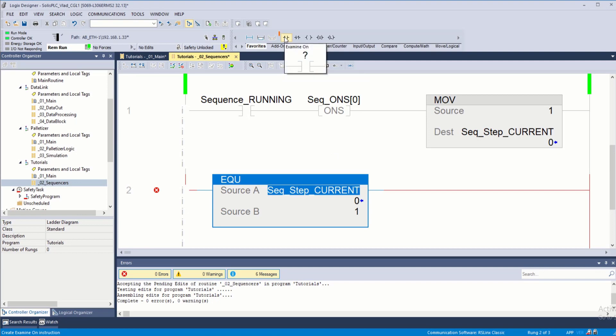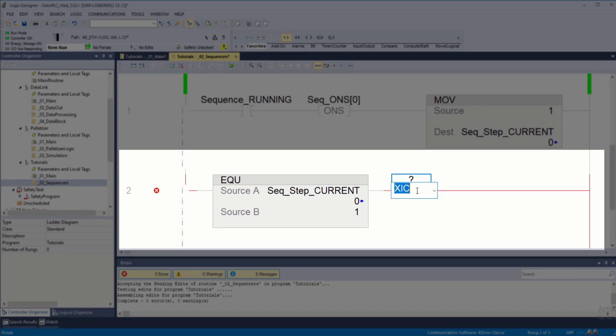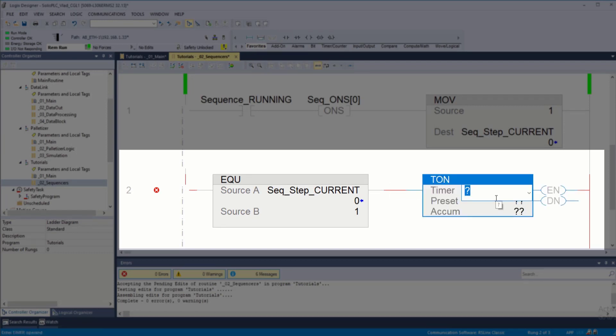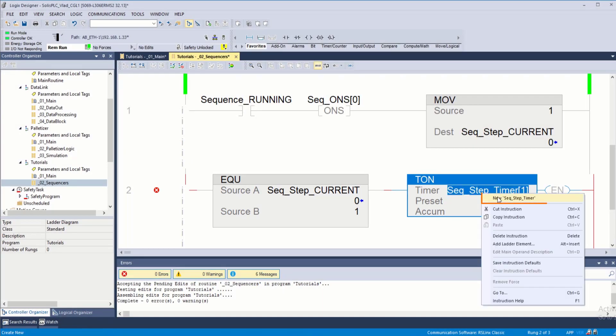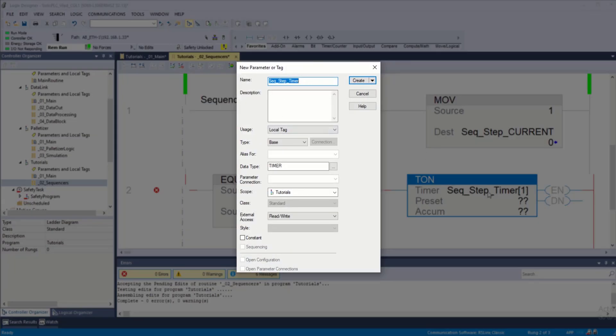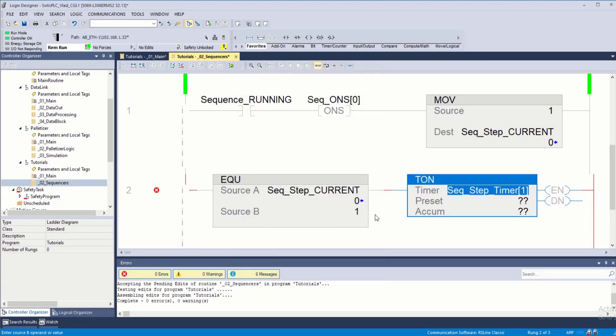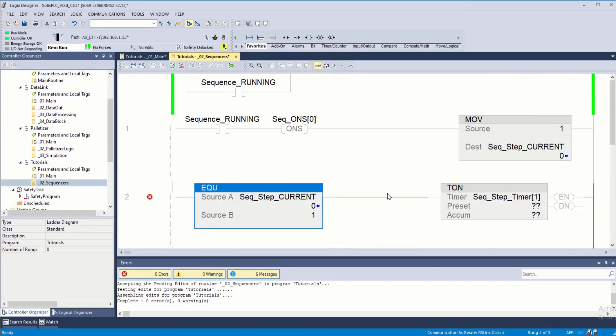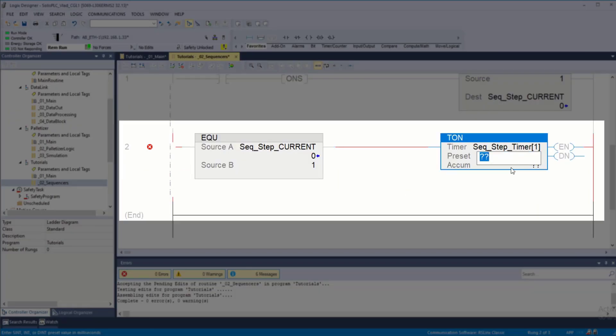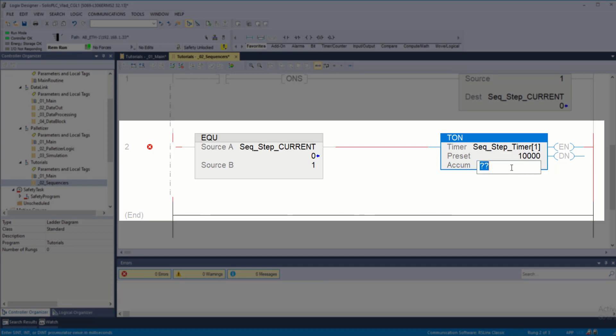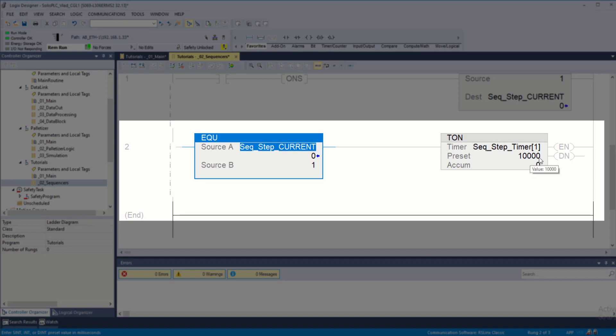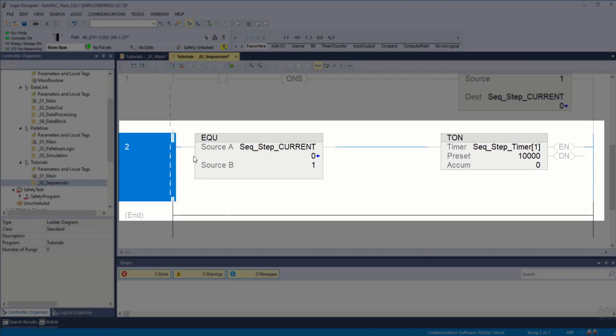Since I'm simulating a sequence, I'm going to introduce different timers for the amount of time that each step should run. This is going to be a TON instruction called sequence step timer, index one — an array of 20 timers underneath tutorials. The preset of our timer dictates how long this step should execute. I'm going to put in 10 seconds, or 10,000 milliseconds. That should be all that is needed.